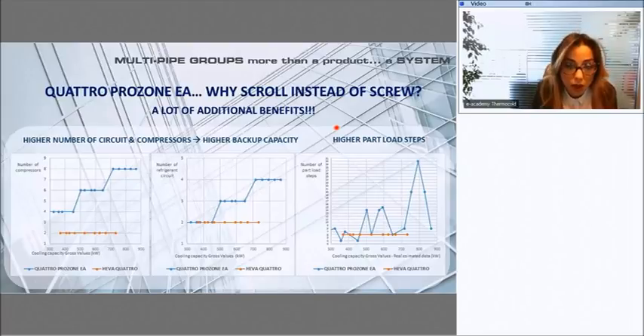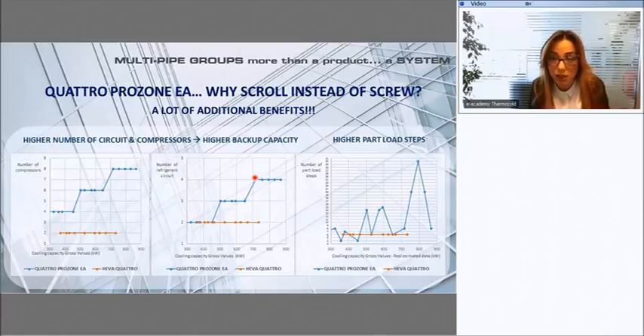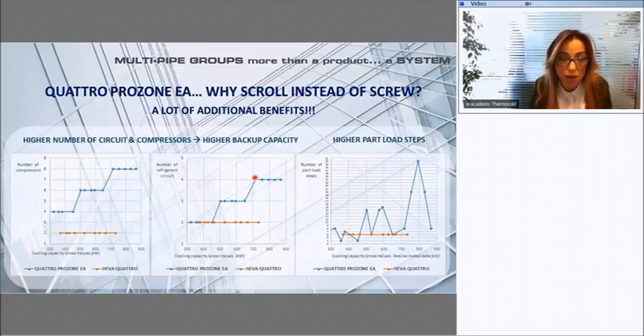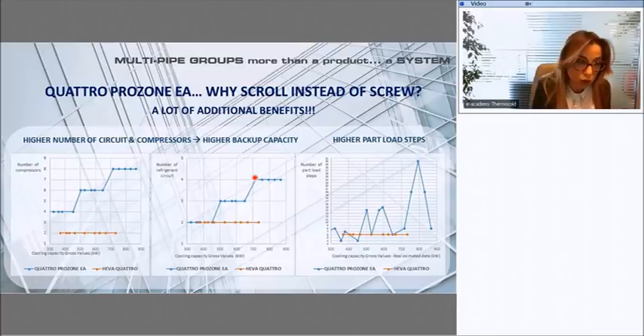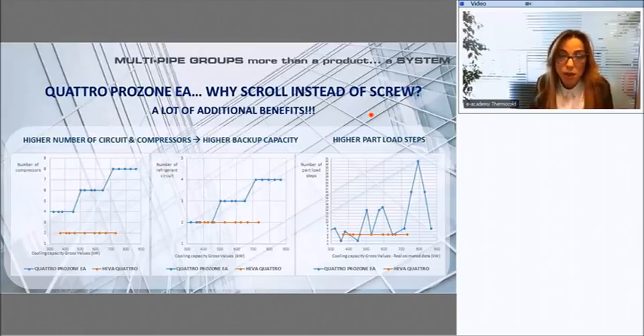In the second graph, we have represented the number of refrigerant circuits. So as you can see, the blue line represents the QUATTRO PROZONE EA, and as you can see, this unit is equipped with a higher number of refrigerant circuits if we compare the same cooling capacity. So, for example, the biggest size of HEVA QUATTRO, providing 700 kW, is equipped with 2 circuits and 2 compressors, while in the biggest size of QUATTRO PROZONE EA, we have 4 refrigerant circuits and up to 8 scroll compressors.